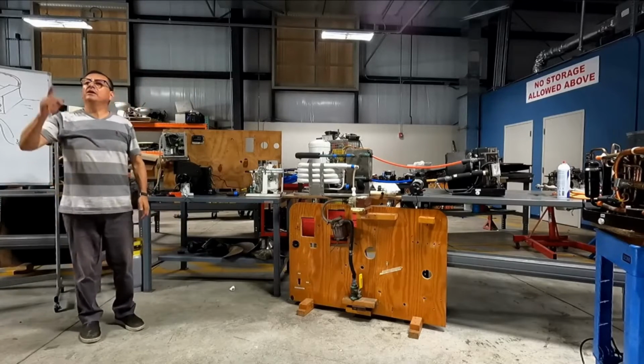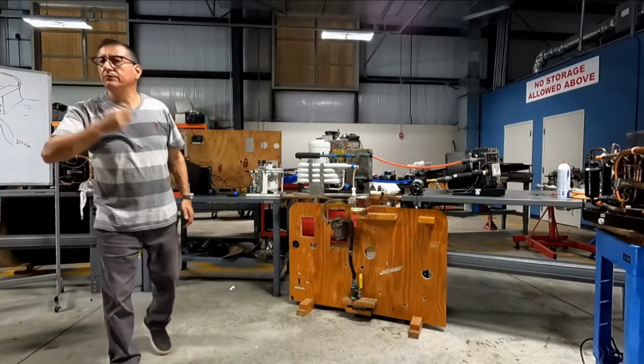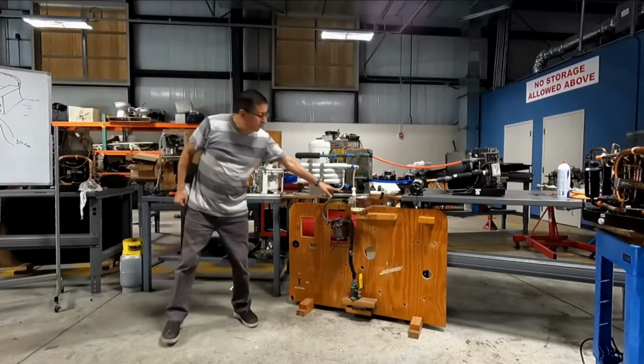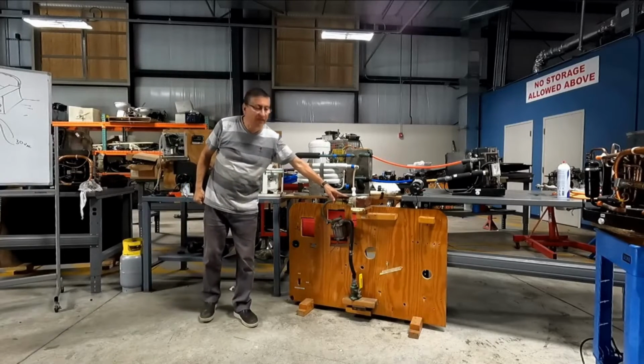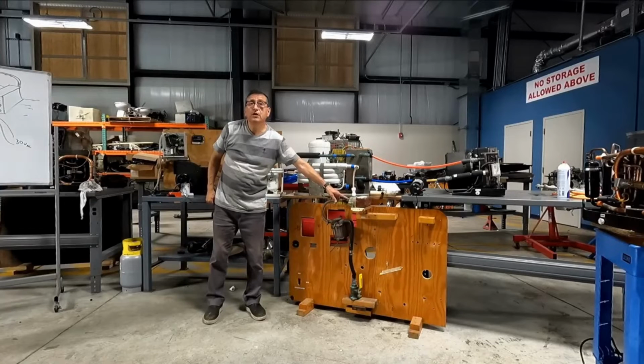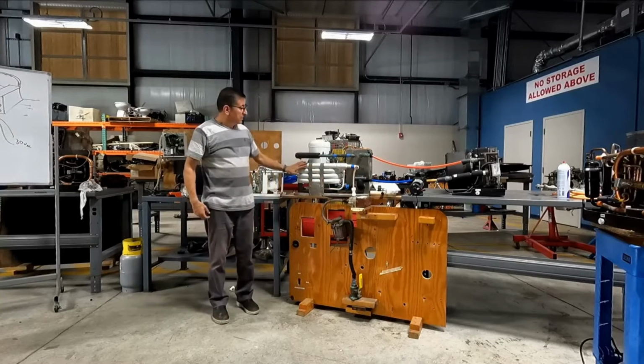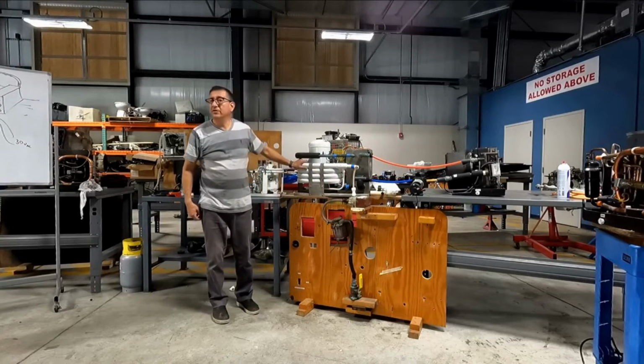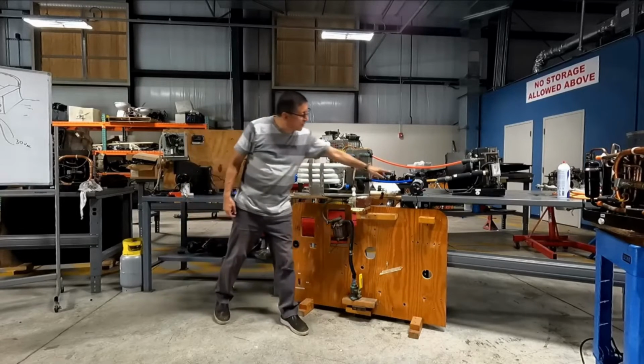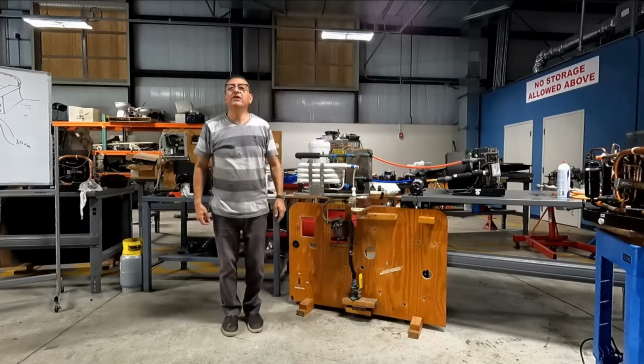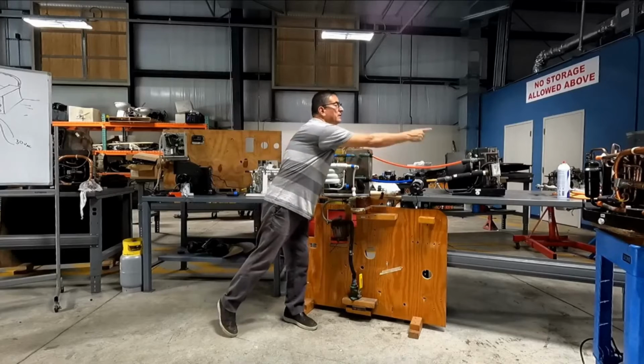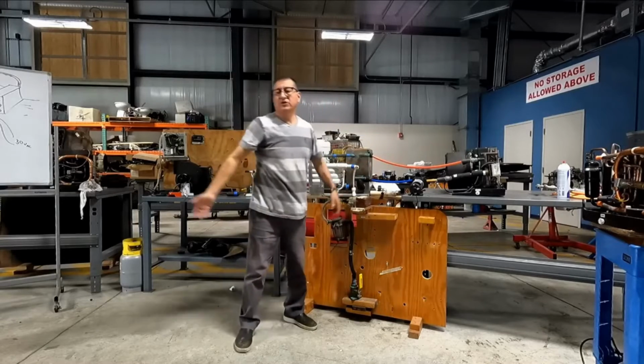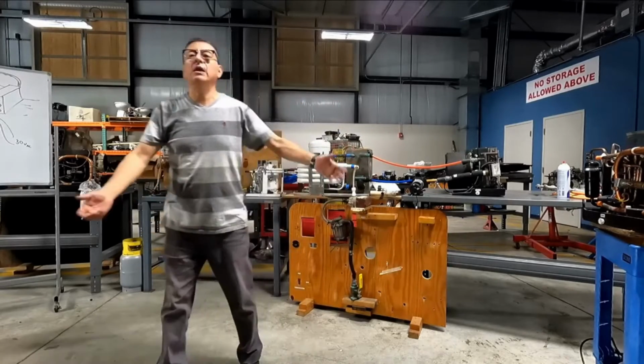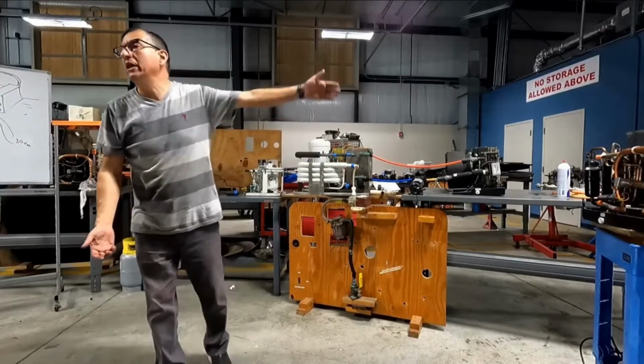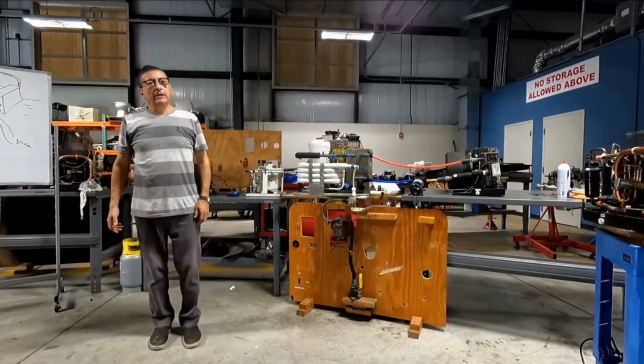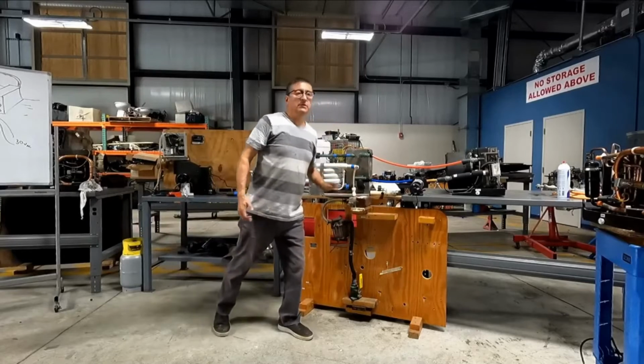In a chiller system, you have two pumps. One pump for the raw water, to cool the condenser. And you have another pump, the fresh water pump, to circulate. It's a circulation pump. Circulating pump, or fresh water pump, or coolant pump, to circulate the fresh water or coolant. Ready? This pump is different than this.